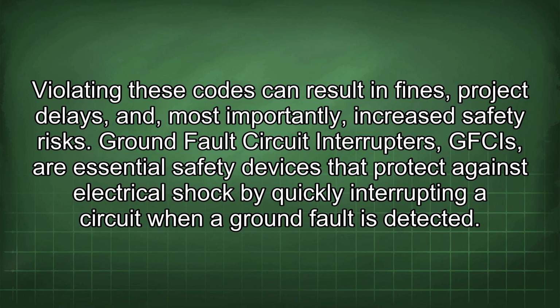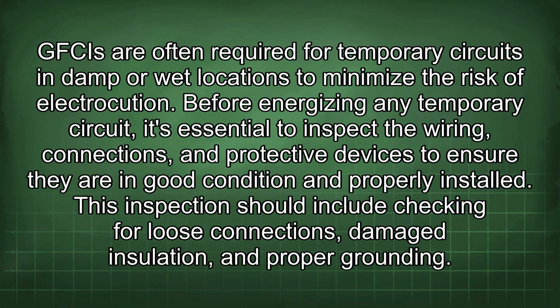Ground fault circuit interrupters, GFCIs, are essential safety devices that protect against electrical shock by quickly interrupting a circuit when a ground fault is detected. GFCIs are often required for temporary circuits in damp or wet locations to minimize the risk of electrocution.